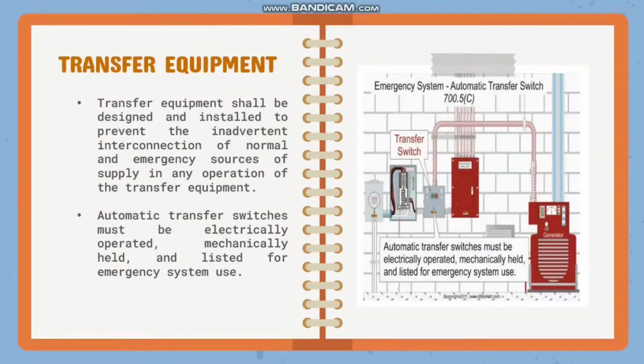Next is transfer equipment. Transfer equipment shall be designed and installed to prevent the inadvertent interconnection of normal and emergency sources of supply in any operation of the transfer equipment. Automatic transfer switches must be electrically operated, mechanically held, and listed for emergency system use. So, ang transfer switch is an electrical device that is used to switch load between two sources. So, kapag nagkaroon ng power interruption, automatically mag-switch siya from normal supply to emergency supply.